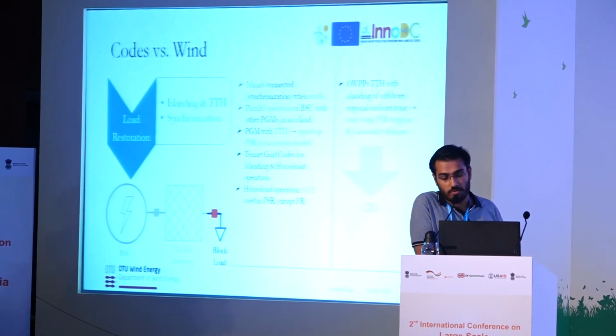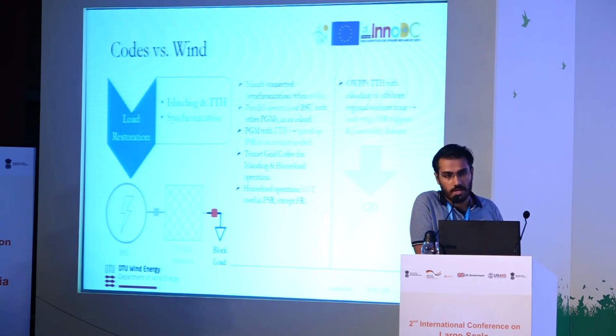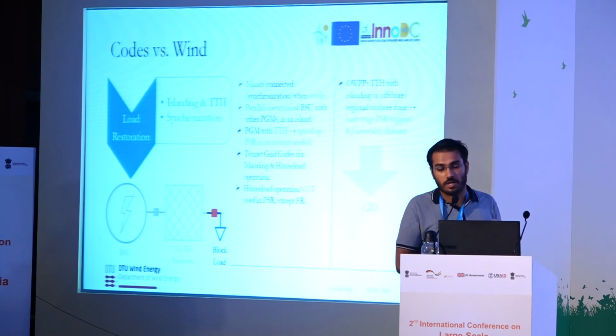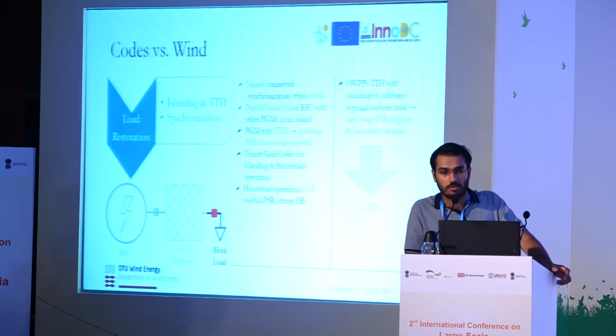Right now, islanding or trip to house load feature of power park modules is not really used in power system restoration, although it's very good because then it saves time to not really ramp up the PPM from start. Except in France, I think they use some trip to house load operation. TenneT has grid codes regarding the connection of PPMs to be able to switch to house load from any operating point, and large 1000 megawatt PPMs to have islanding capabilities. So if offshore wind power plants can do a control being very important, islanded operation of the offshore island, it can help save a lot of time in the power system restoration initial stages.